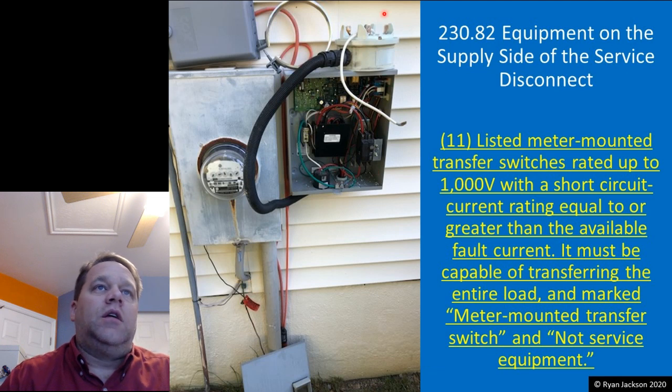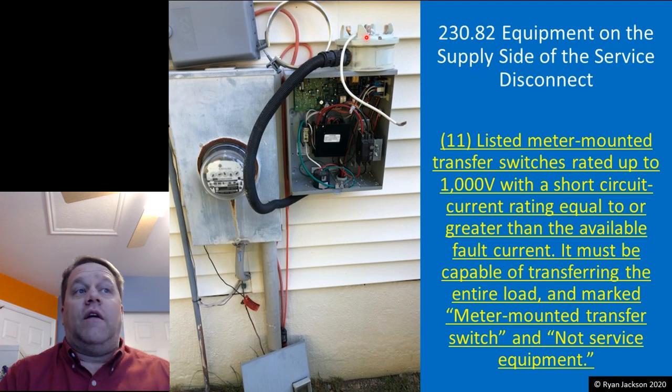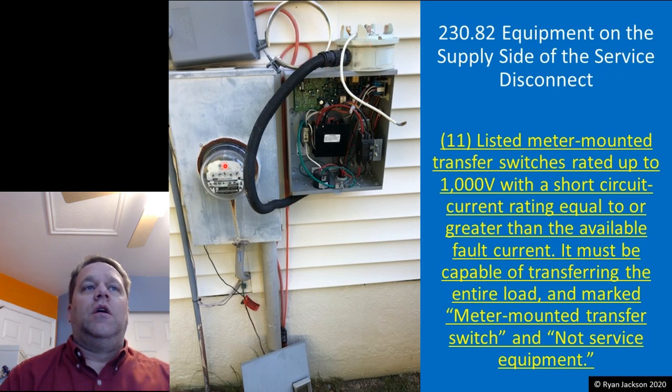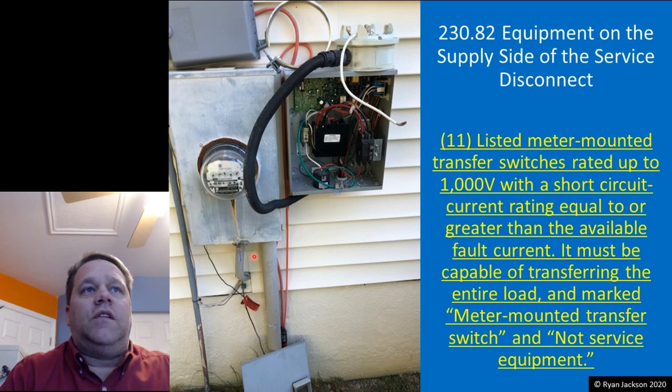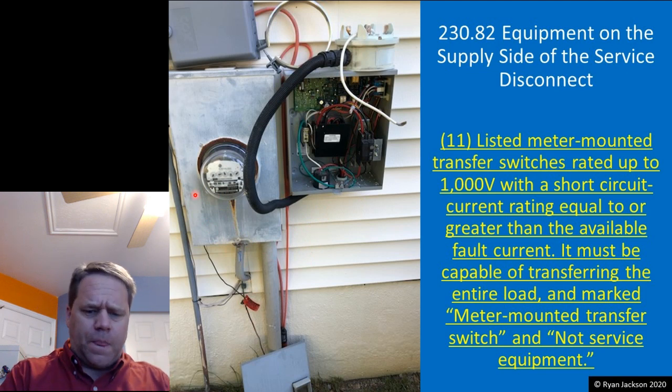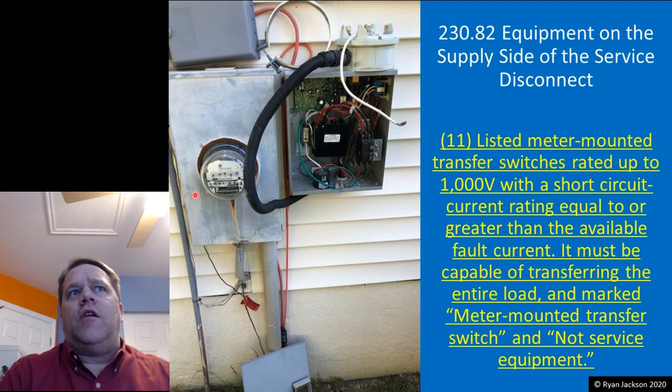So what we're talking about is this guy right here. It's an interesting piece of equipment. Some people have strong feelings about it, and I really don't. I've never installed one myself. But here's the idea. You call the utility, they take out the meter, you slide this apparatus into the front of the meter, and then they put the meter back in, and you plug into it, and it acts as a transfer switch. So it transfers the load. The ones that I've seen are all manual transfer switches. So they're now allowed on the supply side of the service disconnect.